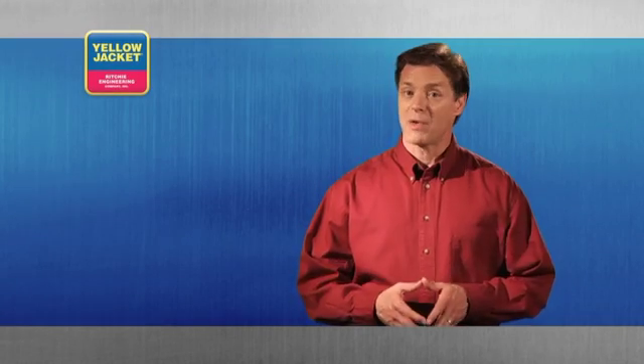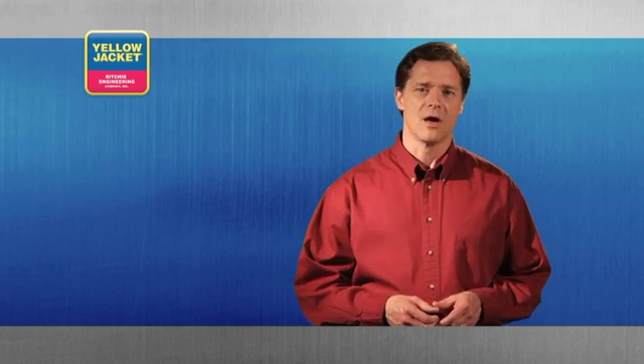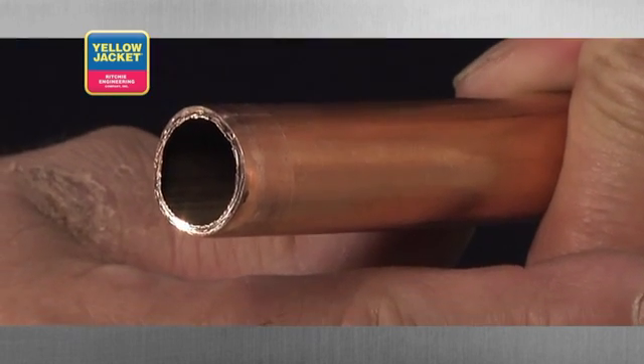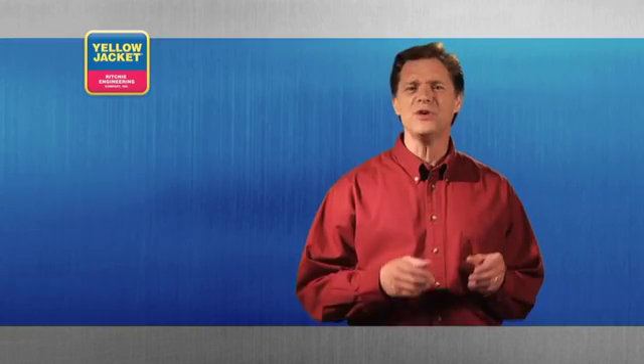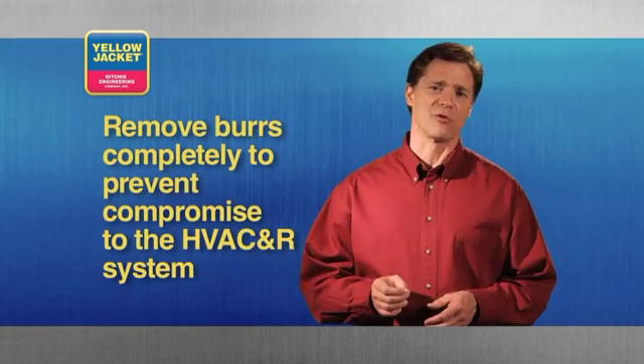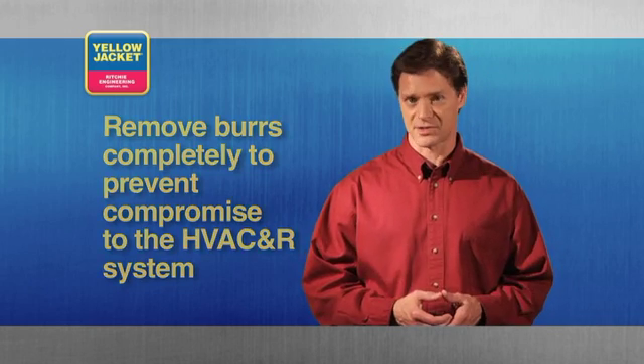Now that the cut is finished, it may be necessary to remove the burrs left behind on your cut. Burrs are the little metal shavings that turn up on the inside wall of your tubing at the cut point. These shavings must be completely removed or they'll compromise the seal and integrity of the entire HVAC and R system.